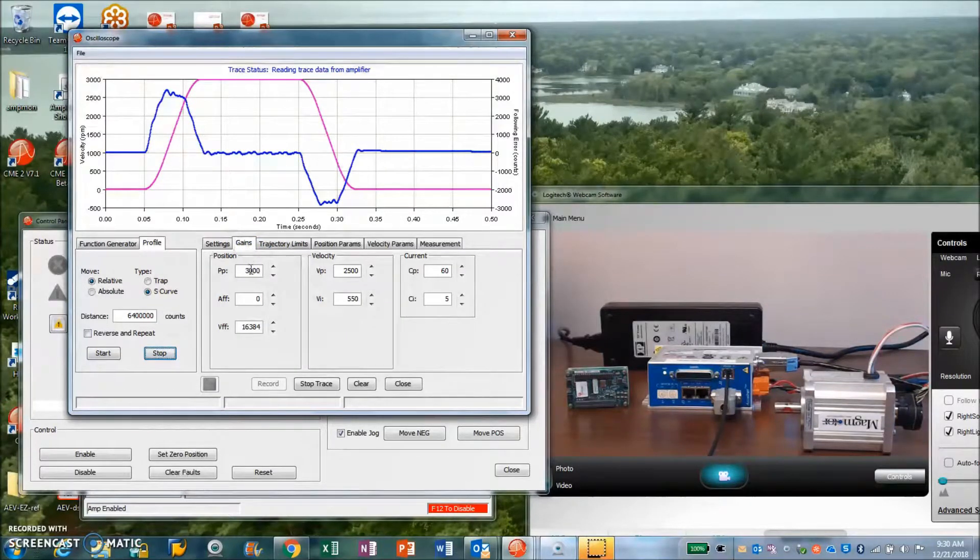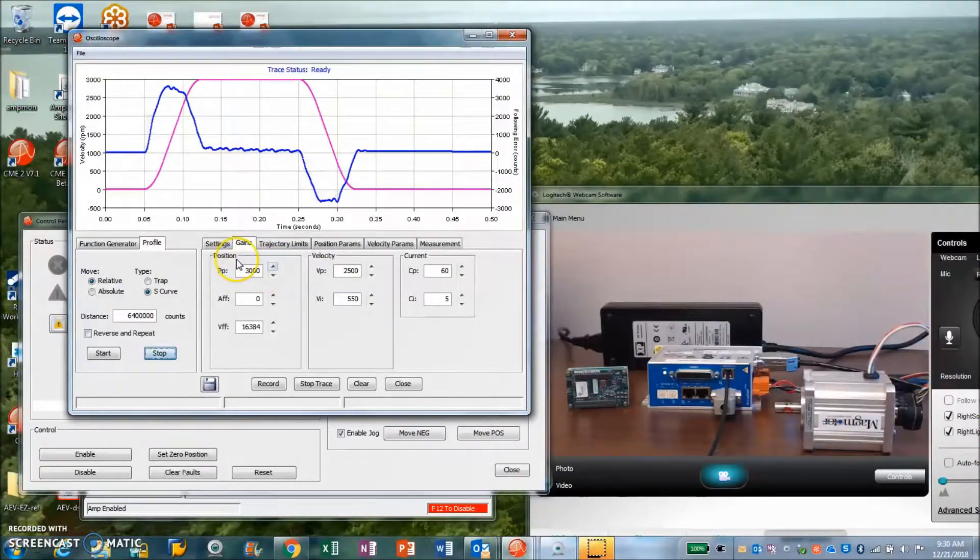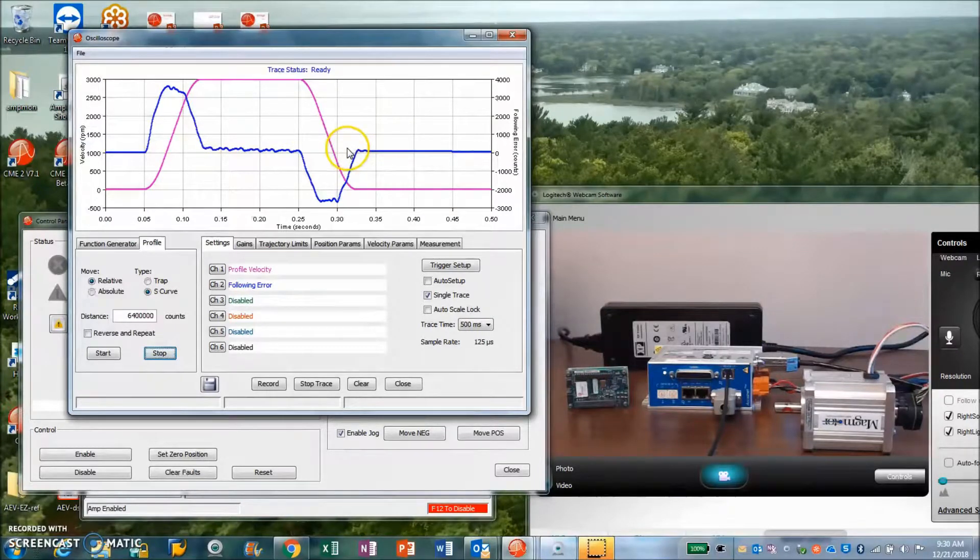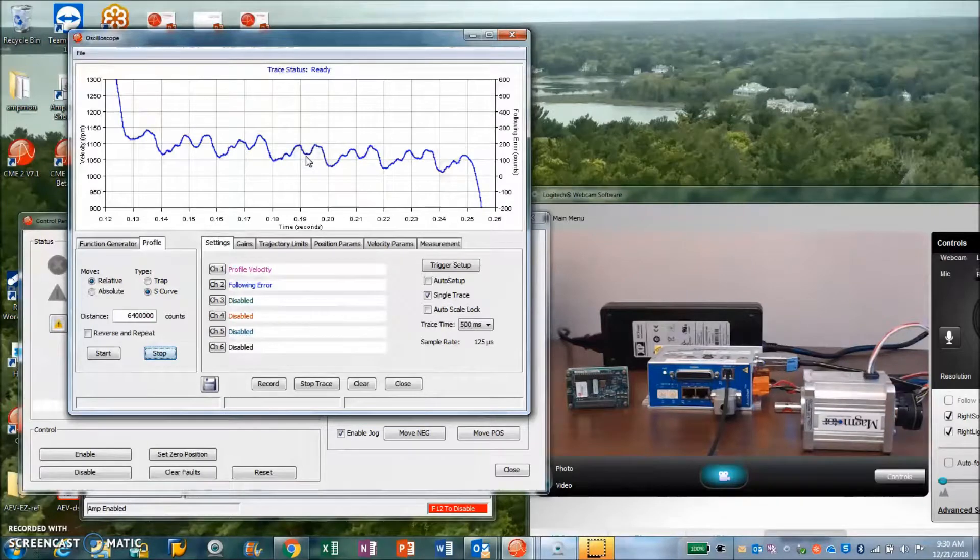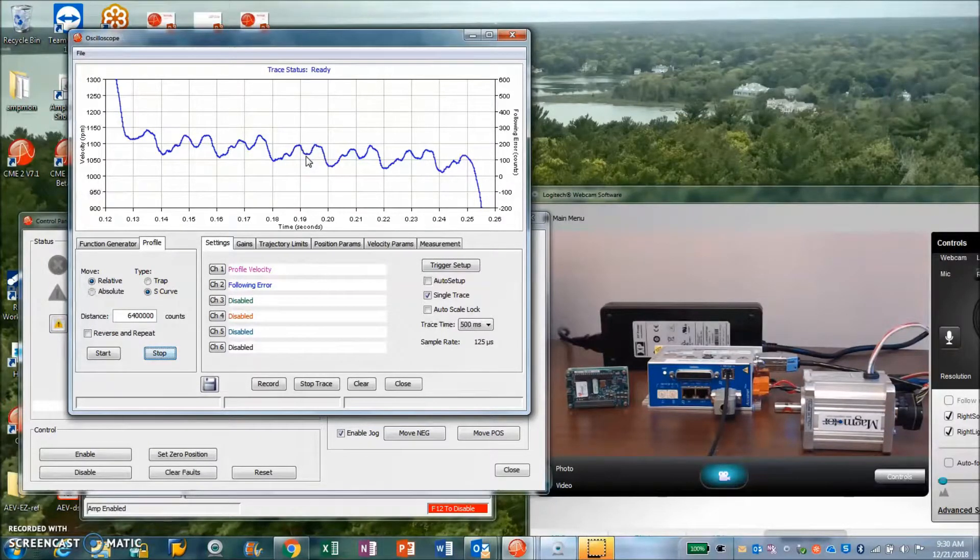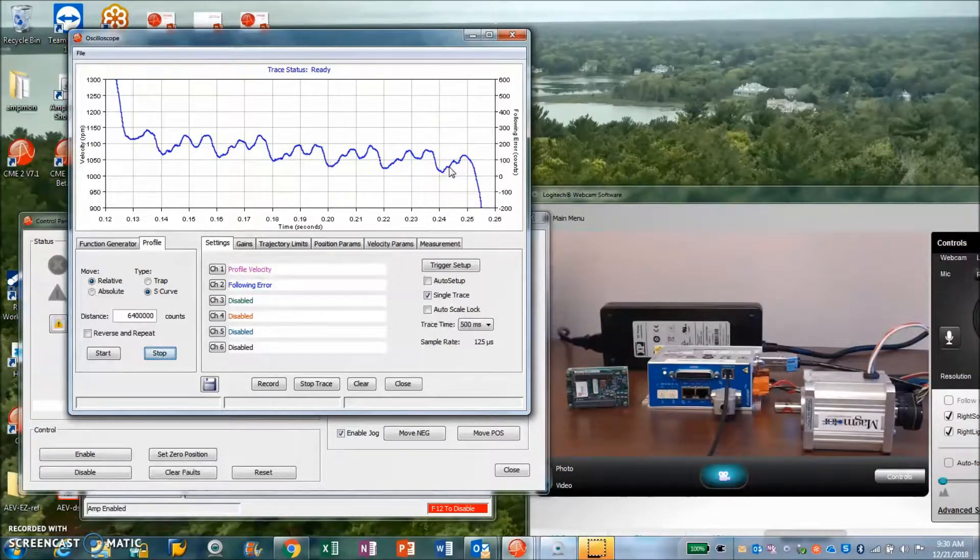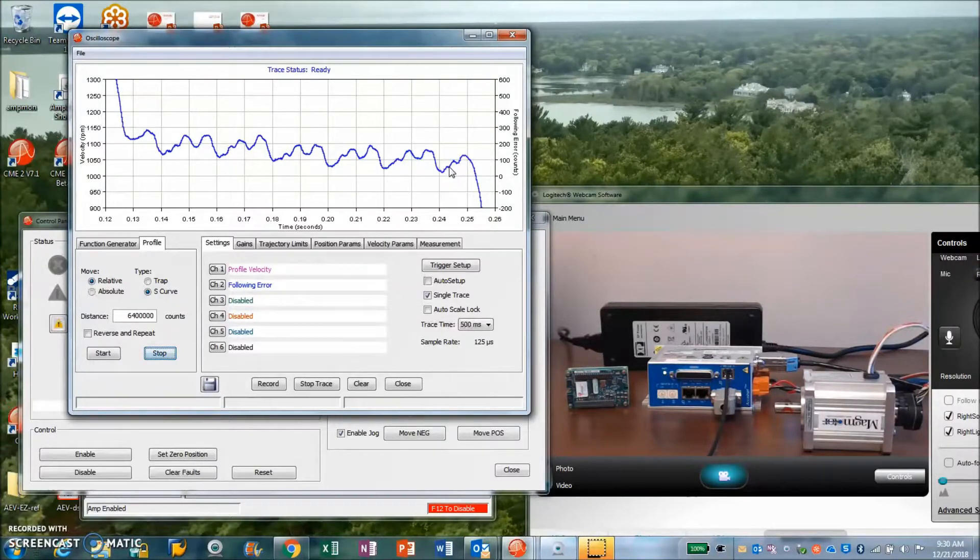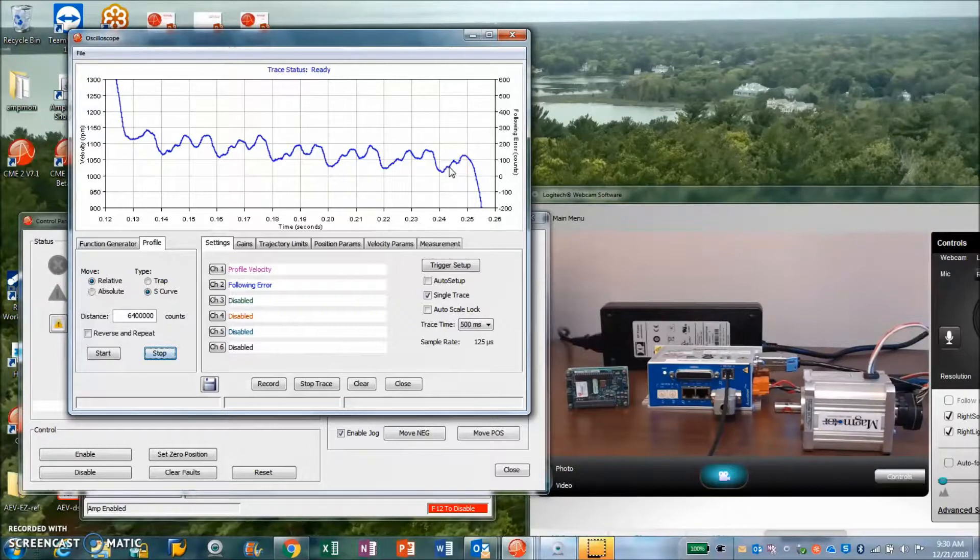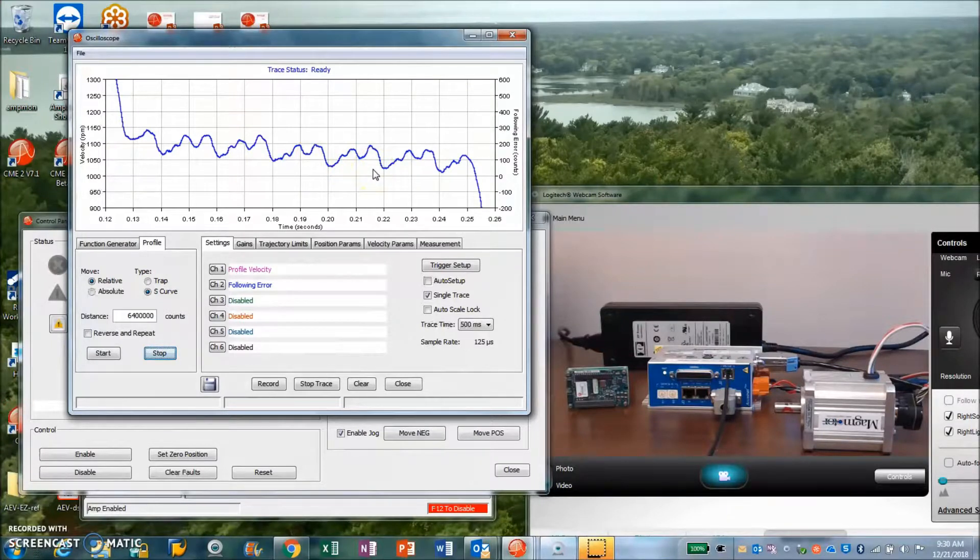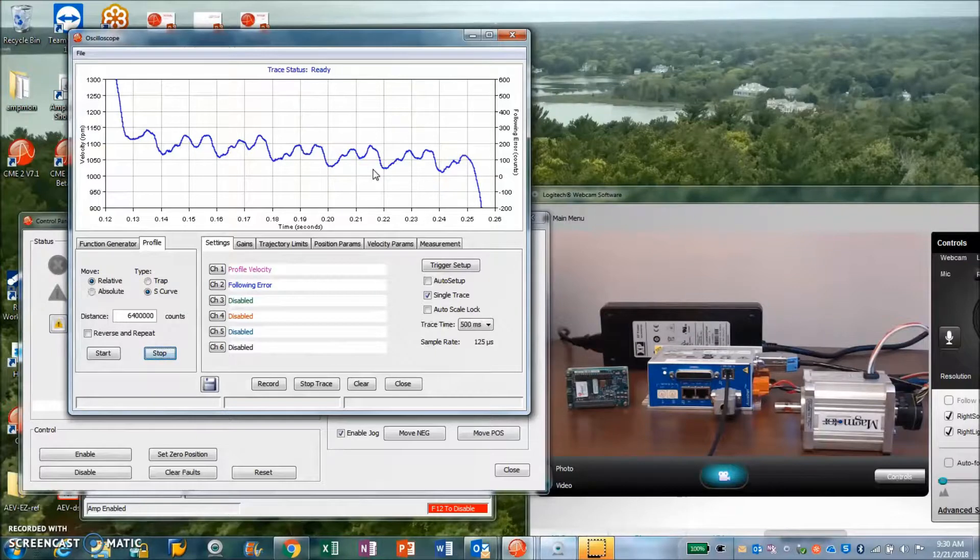I've got PP and the current loop tuning, the velocity loop and the position. That's all tuned up. It's pretty good tuning. The notes of interest are, while we're spinning at a constant velocity, what does the following error look like? If we were running, we'd probably have about plus or minus 50 counts of following error while we're moving. I don't believe this is due to the feedback device. This motor has a little bit of a cog in it. We throw some inertia on it, that'll smooth things out. This cog was in with respect to the electrical cycle, so I already determined that previously.